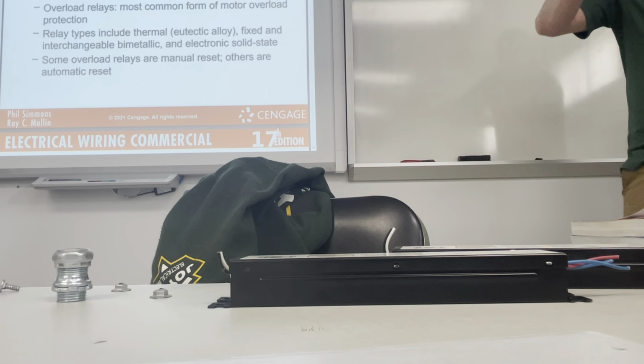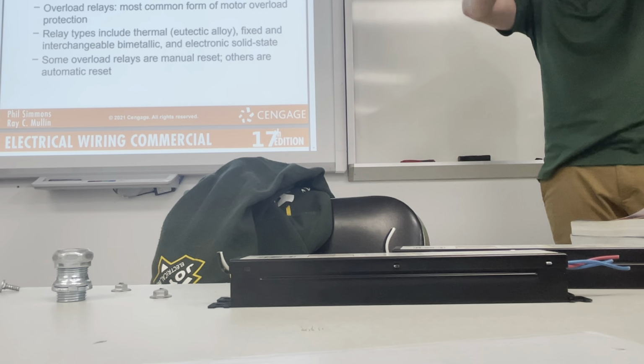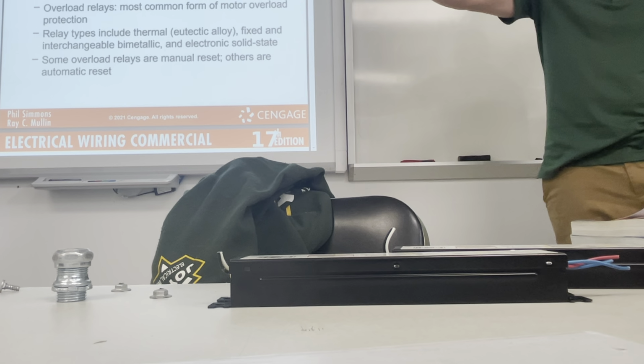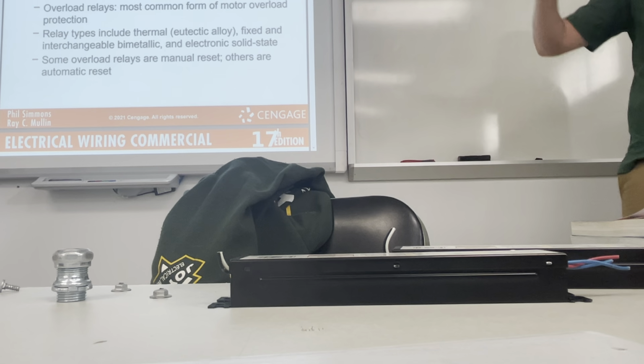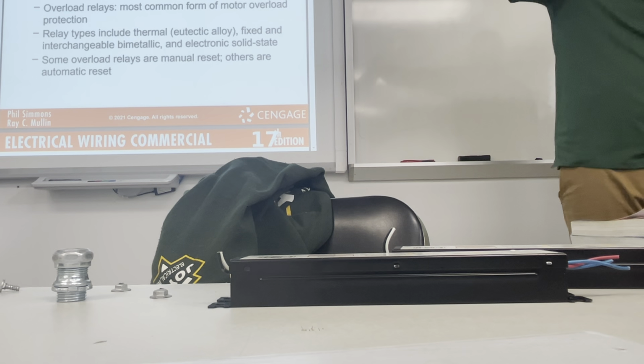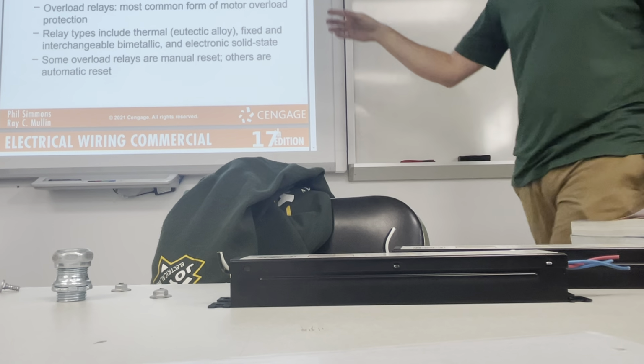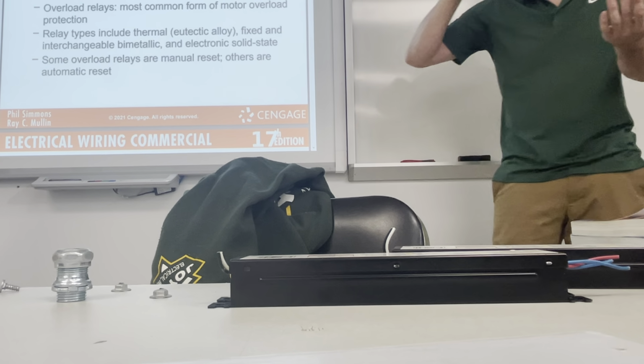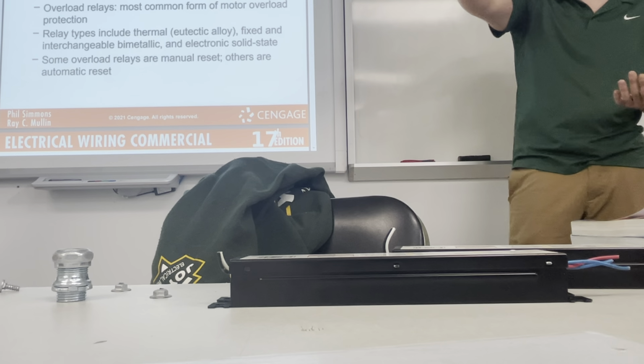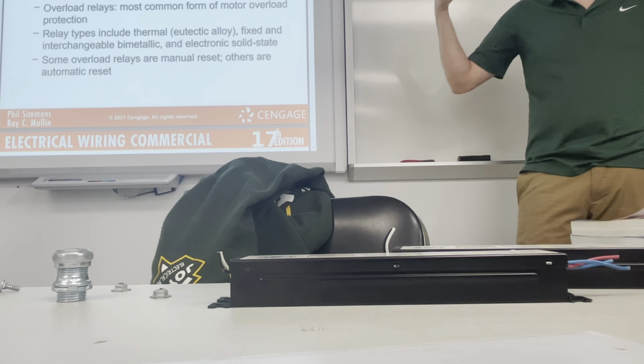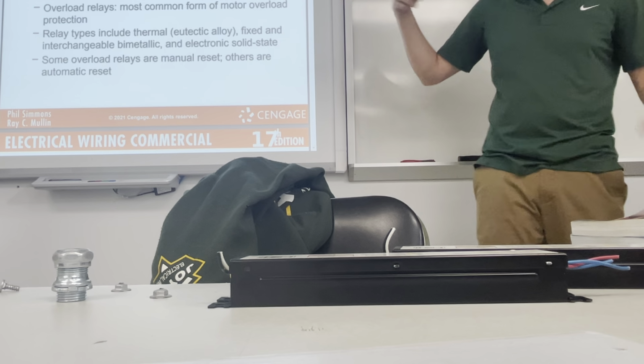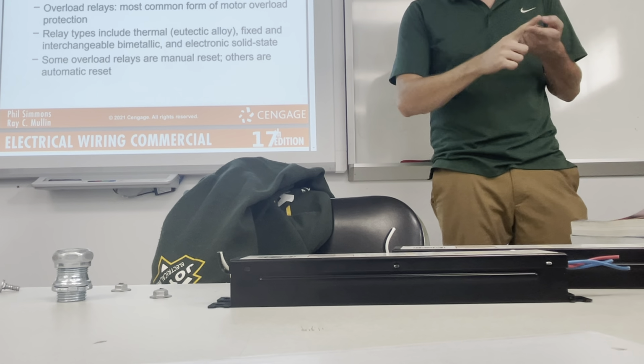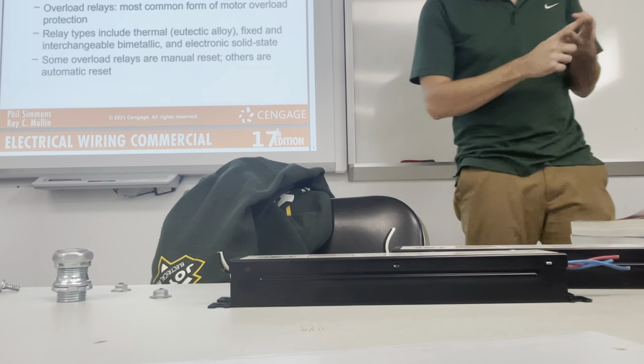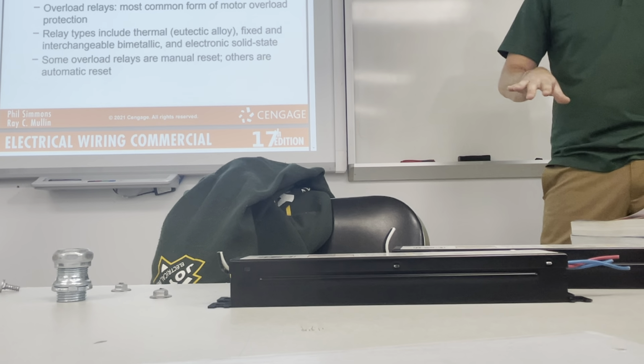And then it starts going. Then it goes back down to its normal amperage level. It might spike up to 50 amps and then go back down to 30. All right. So an overload has to allow that initial startup. It has to allow that high current to go through. It's more of a time thing. If it senses too much heat over too long of a time, it'll pop, killing power to the motor.